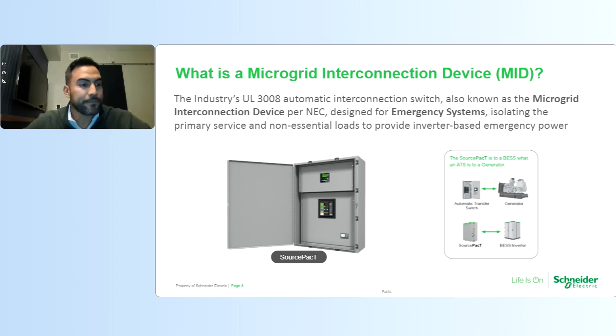So prior, almost like an ATS, if you had an ATS for a NEC 700 emergency system or NEC 701 legally required system, it required an automatic transfer switch there to transfer over to that emergency power system. Here with this automatic interconnection switch, it enables you to disconnect from the grid and signal this battery energy storage system to be utilized for emergency system.